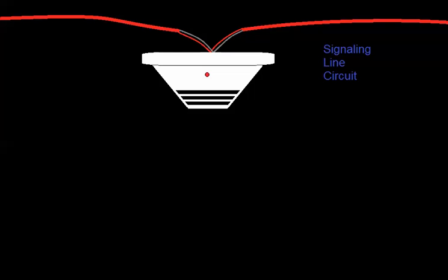The smoke detector is constantly communicating with the panel to make sure it's still on the circuit and still functioning. But when smoke enters the chamber, the smoke detector is not what decides whether or not it's an alarm. What happens is it gives the fire alarm panel an analog value that represents the amount of smoke in the chamber — constantly telling it how dirty it is or how much smoke is present. The panel is what decides whether or not it goes into alarm.